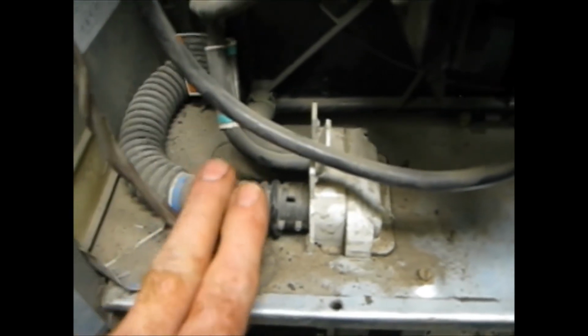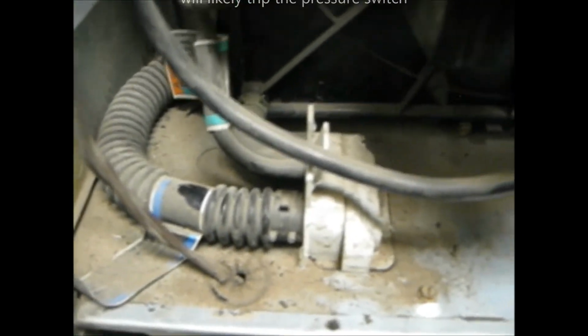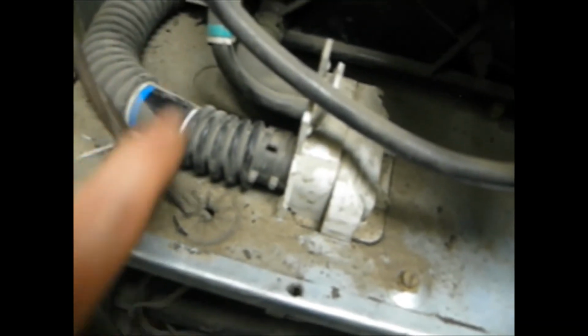Another thing that you might want to be aware of, and this is a point of housekeeping every year, is to check your condensate lines. Now, high efficiency furnaces give off a lot of water, and that water is collected down here in this water trap and flows down here to this little pump, and it looks like they have this hose going outside. Well, one thing you want to make sure is that this pump works. It has a little float down inside. When the reservoir fills up, it'll turn on and eject the water outside. Sometimes you might have an inside drain that is where the water will be injected to. But it's not a bad idea to remove these hoses and just to make sure, clean things out. If water were to back up from the condensate trap back through these hoses, it's going to interfere with the pressure switch. So that's just one of those little things you might want to do each year, is to check to see if water is backed up in these hoses.